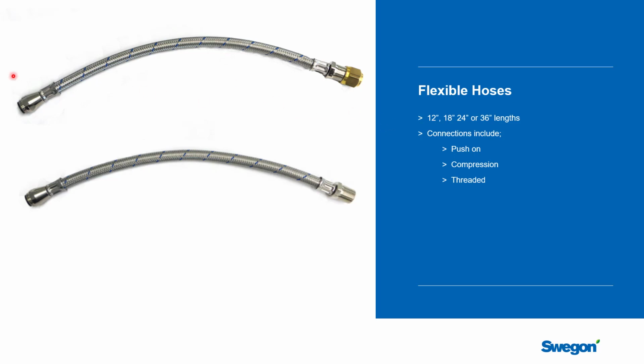In terms of the connections, these are push-on fittings. They could be John Guest style or SharkBite or whatever the manufacturer is at one end. And then at the other end, you could have a threaded connection that could be used with a coupling onto a beam that has a brazed threaded connection, an MPT connection. Or you could have this, which is a compression fitting that would go straight on the copper and could be tightened up and would pinch down on the copper. They're all available.